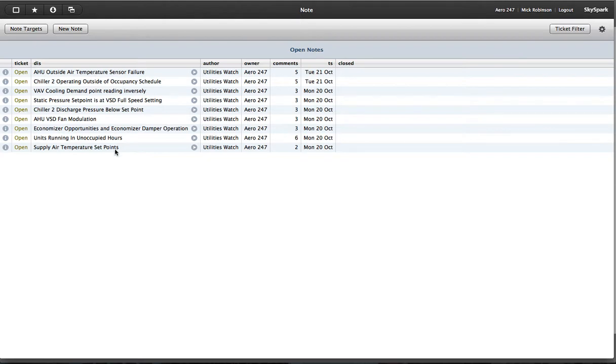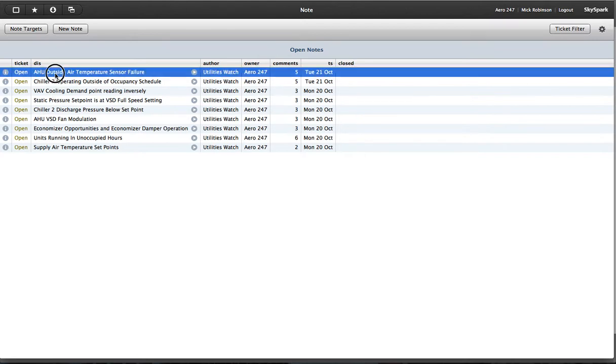With these key opportunities that we've identified, this customer implements all of these. The estimated savings in energy consumption is between 20 to 25%. So there's some significant opportunities here. And it starts to flag things. For example, this opportunity here, the outside air temperature sensors failure.